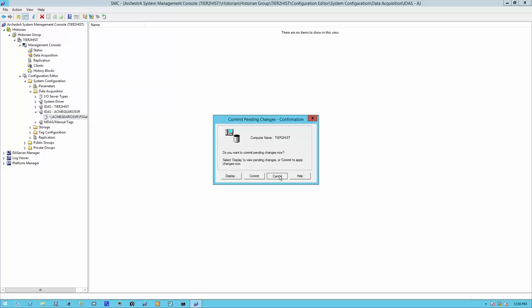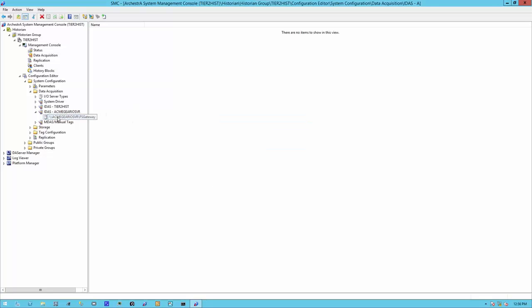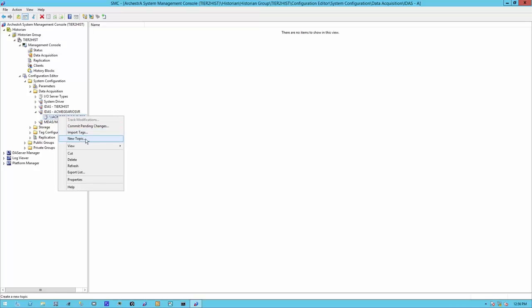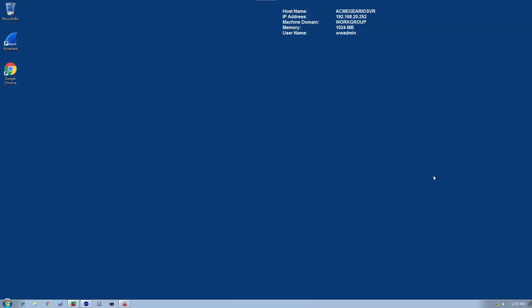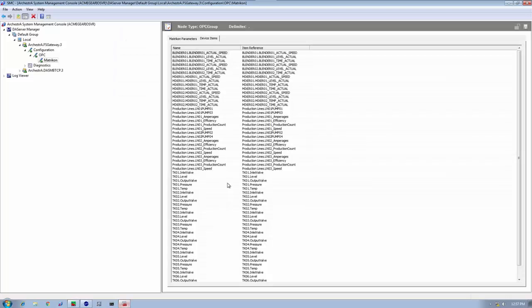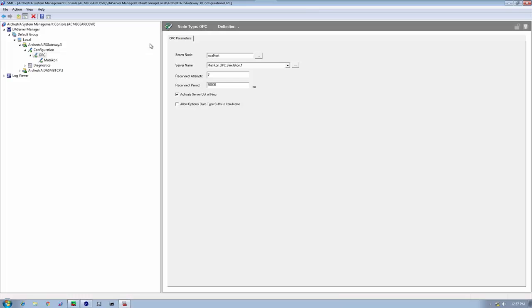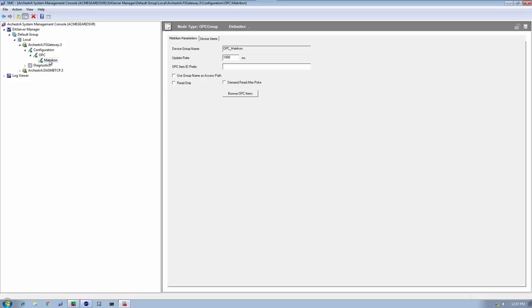The previous changes are still being committed. But in the meantime, let's create a new topic. To verify the topic, let's head back to the IO server. On the IO server, we have our Matrikon OPC FS gateway OPC server that we're talking to. And this is our device group, OPC underscore Matrikon. So this is what we're going to put for our topic as far as our historian IDAS is concerned.